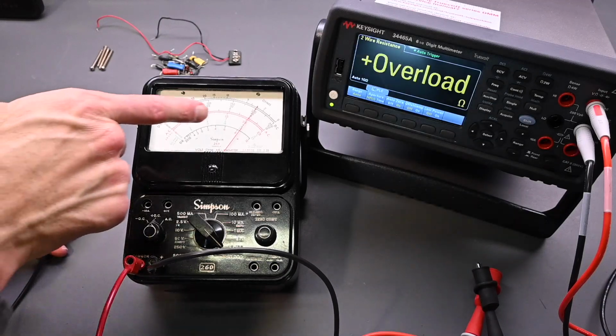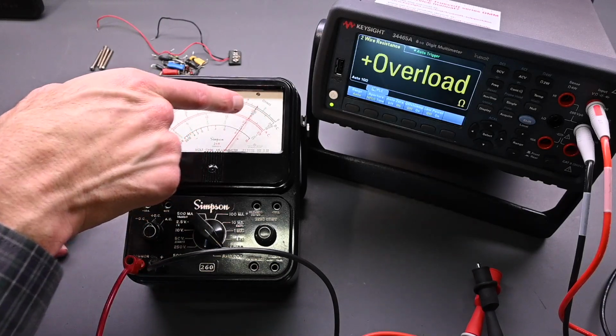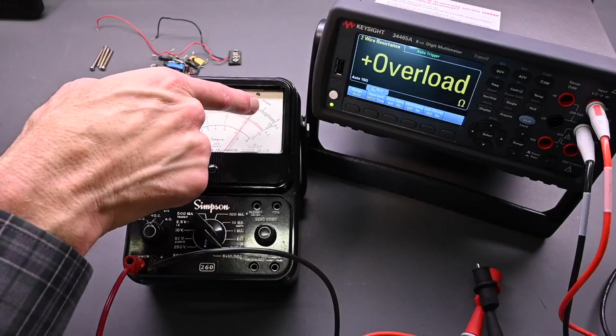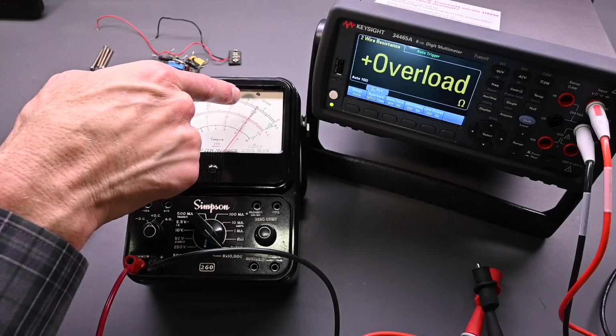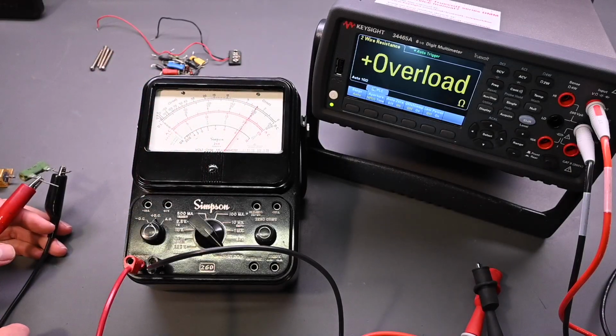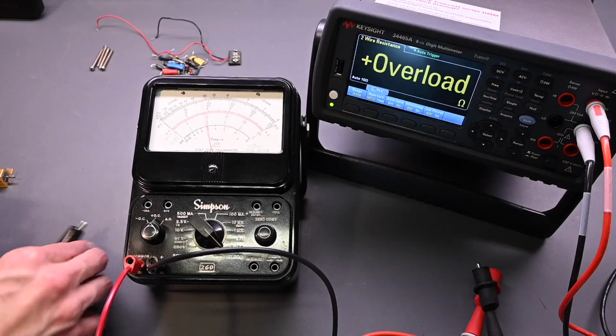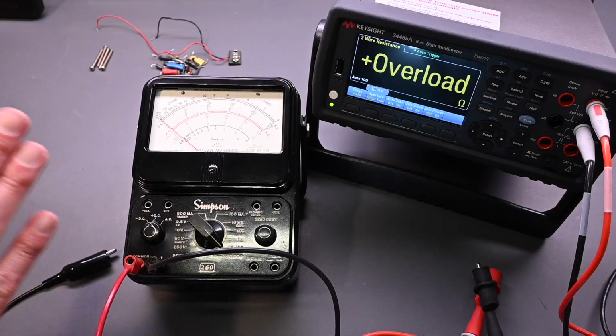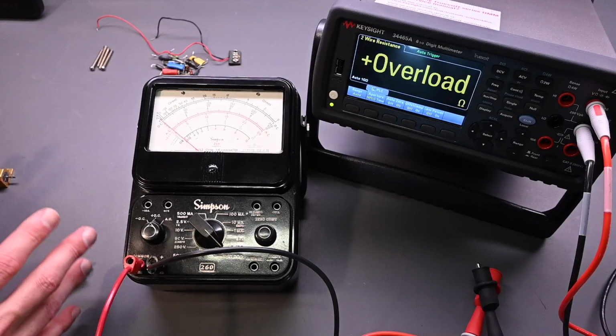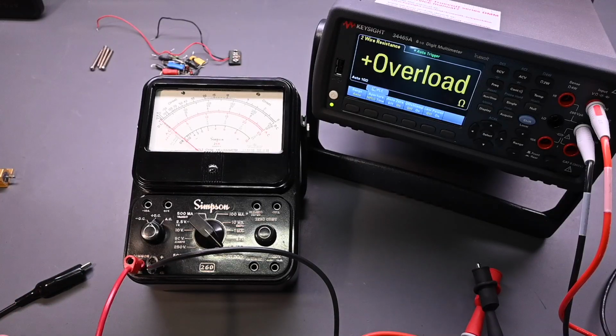So that looks very good right there. Again, we're on this top scale and it's times 100, so that's 200, and then 300, 400, and 500. So that's very accurate. That looks good. No problems with that. So that first resistance range, perhaps just ever so slightly off, but it's not far. You know, it is very close.